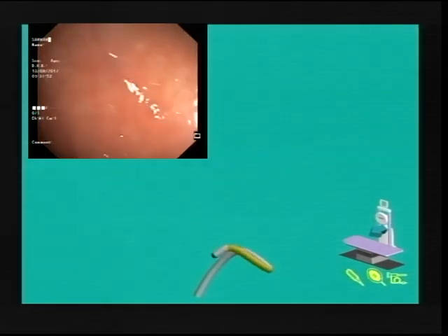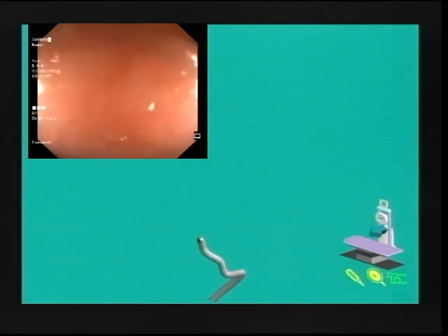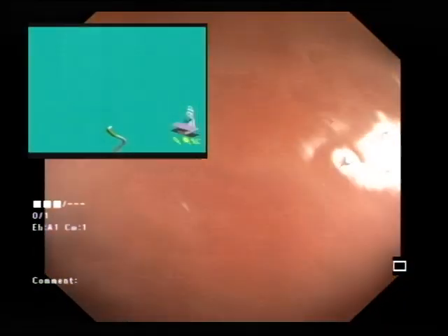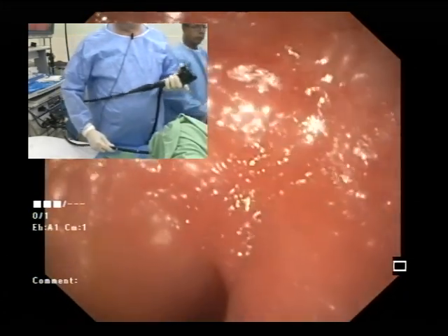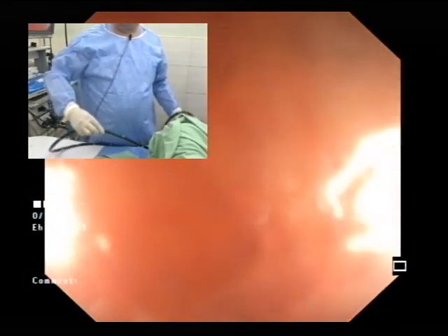Right. Can you see how the scope guide has got a brown bit? A brown piece. Now it's all grey. Now it's gone brown. Where it's grey, it knows where it is. Now the scope itself, I don't know how technical you want me to be, has numerous rings around it every few centimetres, every few millimetres. Those rings 3 times a second send a magnetic signal to the receiver dish, and that's why it gives a real-time image.